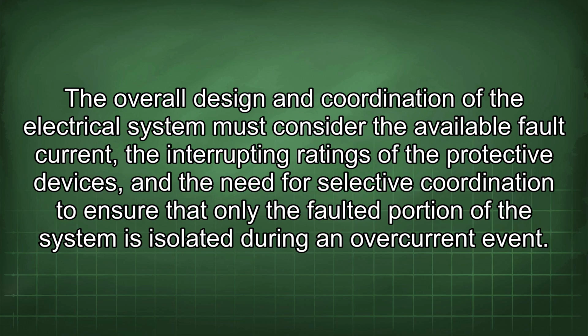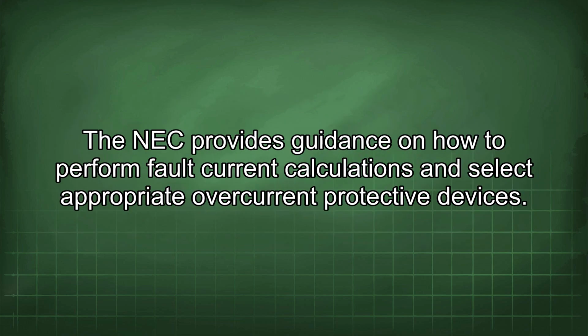The overall design and coordination of the electrical system must consider the available fault current, the interrupting ratings of the protective devices, and the need for selective coordination to ensure that only the faulted portion of the system is isolated during an overcurrent event. The NEC provides guidance on how to perform fault current calculations and select appropriate overcurrent protective devices.